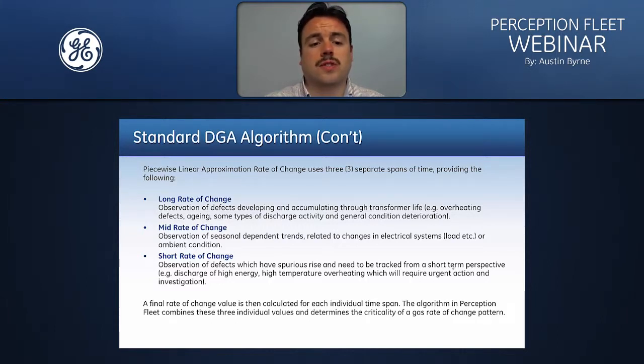And then our short rate of change is observations of defects which have spurious rise and need to be tracked over a short time, and these are the ones that are seen to be the critical. So they show discharges of high energy, high temperature overheating, and generally any kind of increase that is detected over a short period of time needs to be investigated immediately. Once all this information is taken in and calculated, a final risk evaluation is given to the asset for the standard DGA algorithm.